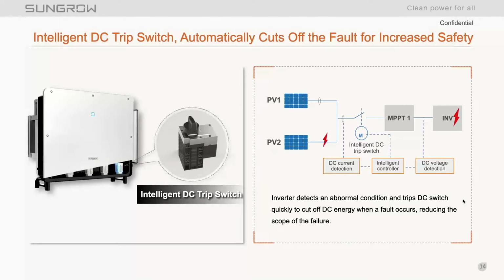So getting a little bit more into the weeds here with the intelligent DC trip switch, it automatically is going to cut off the fault, as I mentioned, for increased safety. So when the inverter detects an abnormal condition, it's not only going to trip the DC switch autonomously, but it's going to remove any voltage that may exist on that line so that we can safely troubleshoot and de-energize that entire circuit. So it operates in concert with the DC current detection circuit, the DSP or the intelligent controller, and the DC voltage detection circuit. So everything combined there, it's kind of a suite of protection. And as I mentioned, the SG350HX is going to have more than one DC switch. It's probably going to have 4 of them that are kind of divvied up to help break up the MPPT and reduce the incident energy on all of that.